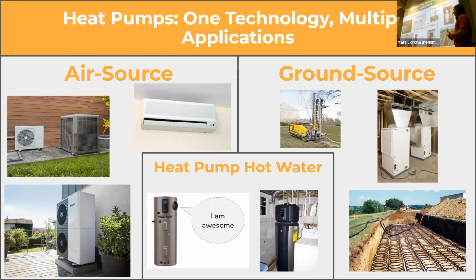Heat pumps are very energy efficient, and they're all electric. One of the main differences between a heat pump and a furnace that burns fuel: a furnace creates its own heat by burning fuel - the energy is trapped in the molecules of the fuel, and when the system burns it, it releases that energy to heat your house. Heat pumps don't create any of their own heat, they just move heat from one place to another. Because they're just moving heat, that's part of what allows them to be so efficient - they could be 300 or 400% efficient, meaning for every unit of energy you use to power the system, you get 3 to 4 times as much thermal energy moved into your house. So very, very efficient.